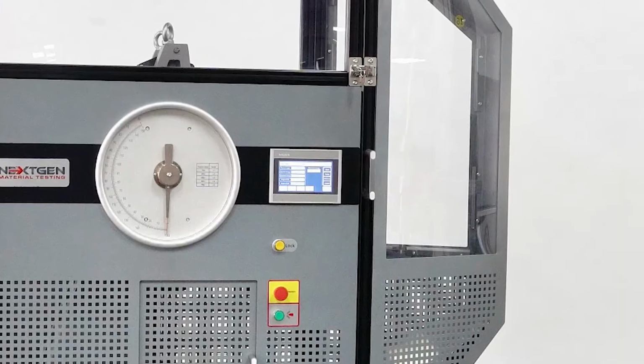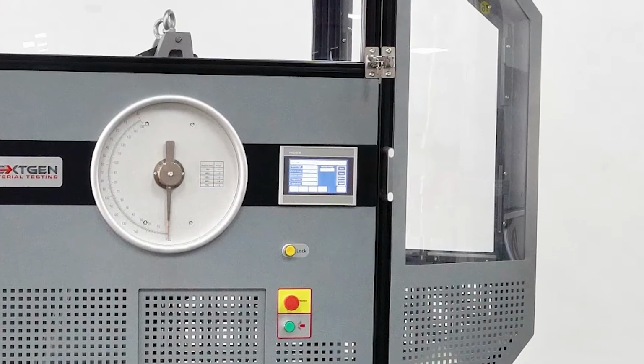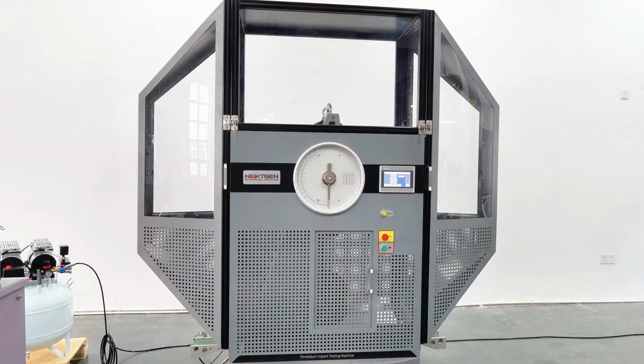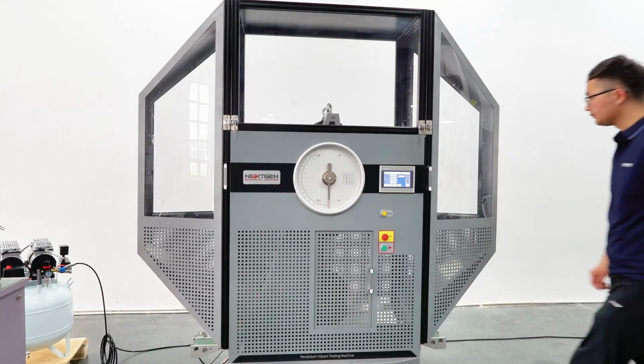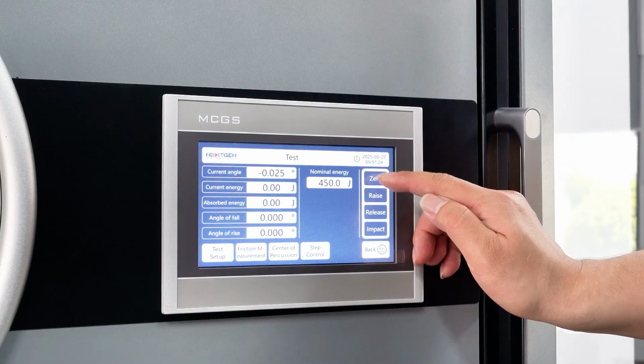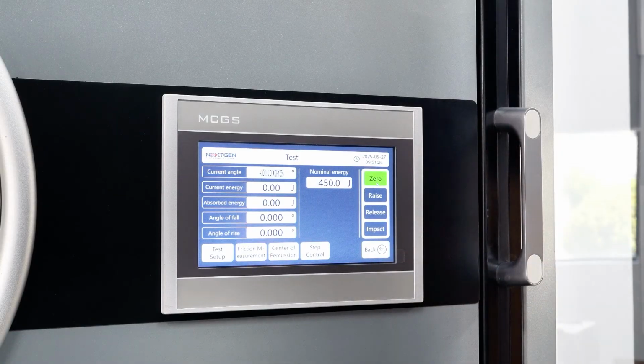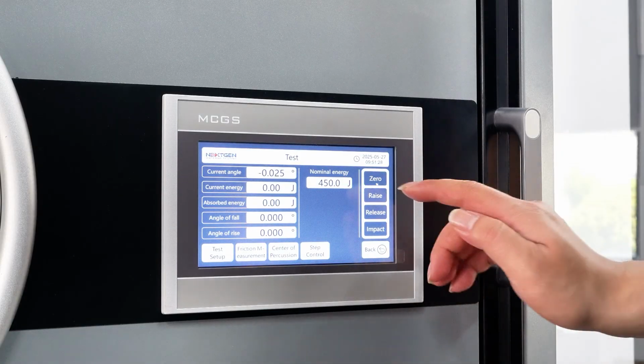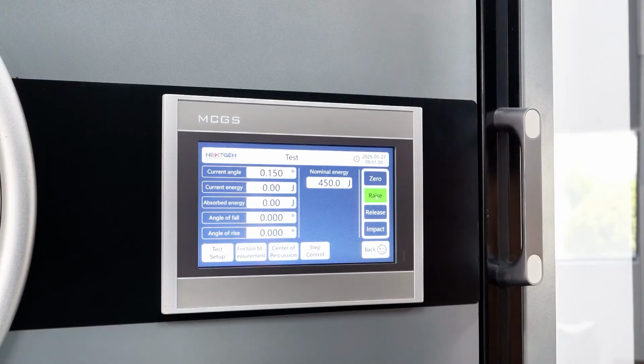From here, you can operate everything using the built-in touchscreen. Before starting the test, make sure the pendulum is still and in the vertical position. Then press Zero to reset the angle. Tap Raise to bring the pendulum up to the ready position.